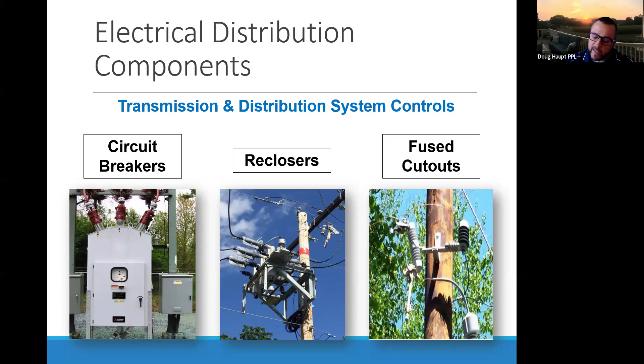So everything in red is owned by the utility. Okay. Here's your top wires, which are energized. So you could have one wire up on top. You could have three wires. You could have two wires up on top. Top wires are the energized wires. You have your fuse, which is protecting the transformer, and this wire is our neutral. A neutral you must consider as energized. It is our return path.